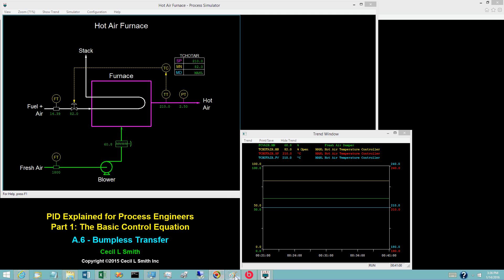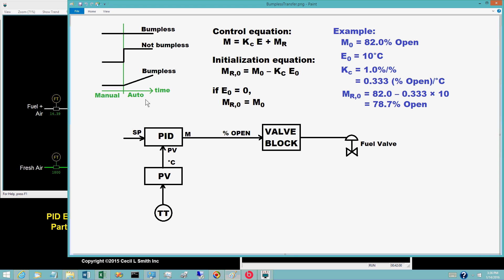For a PID block, what is meant by bumpless transfer? It means that no abrupt change occurs in the controller output at the instant the mode is changed from manual to auto. There are three possibilities for the behavior of the controller output. One is that the controller output is constant prior to switching the mode and remains constant at this same value subsequent to the switch — clearly, this is bumpless. Another is that the controller output changes abruptly at the instant of switching the mode to auto — clearly, this is not bumpless.